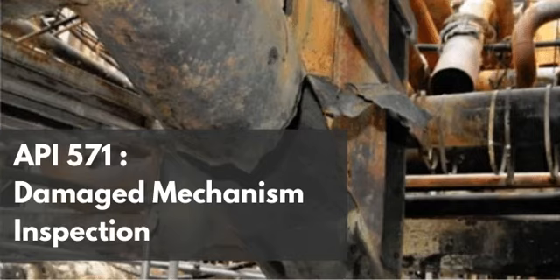Right. Exactly. You meticulously clean the inner surface of the rolled tube. Then you spray a brightly colored, highly fluid liquid dye onto the metal. Because ammonia SCC creates tight surface-breaking networks, capillary action forcefully draws that liquid dye deep down into the microscopic cracks. It pulls the liquid in like a sponge. Yes, exactly like a sponge. Then you wipe away all the excess dye from the surface, leaving the metal looking clean again. Then you spray on a fine white powder called a developer. The developer acts like a blotter.